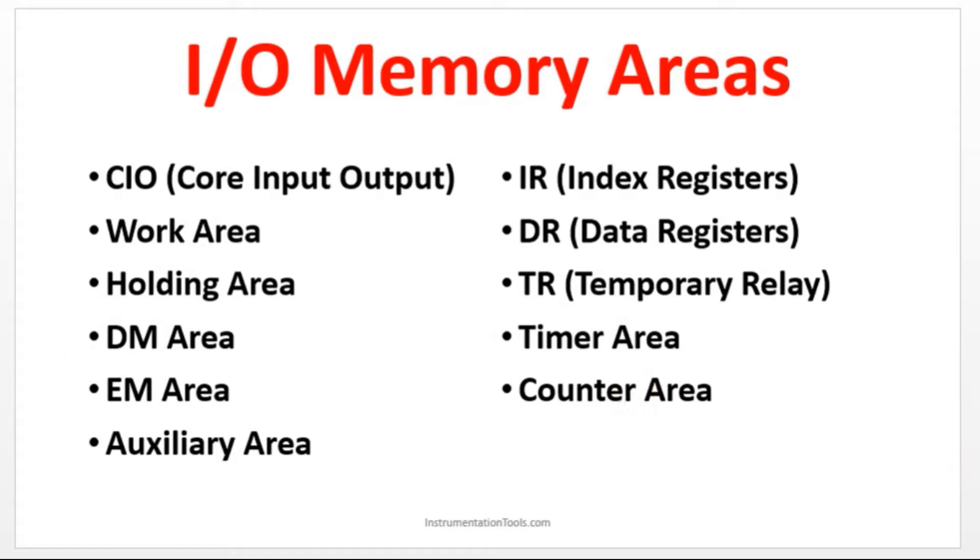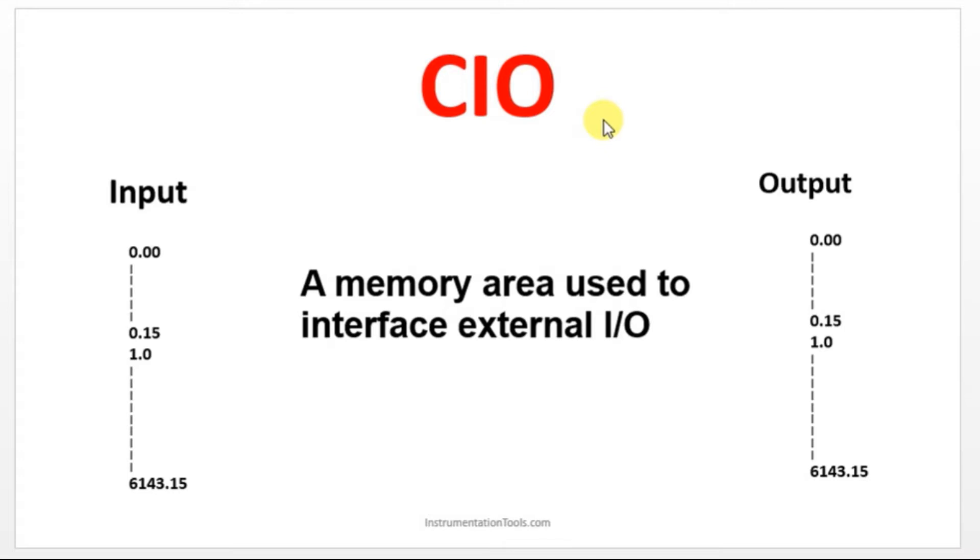Let us see about that first: Core Input and Output. The input addressing in Omron will be starting from 0.00. This 0 is the channel number and the next 0 is the terminal number. Like that it will start. 0.00 up to 16 we are having here. 0.00 to 0.15 is the first channel. Next, it will start with 1.00, like that it will go. That's it for input addressing. Input address of Omron will start from 0.00 and it will go till 6143.15.